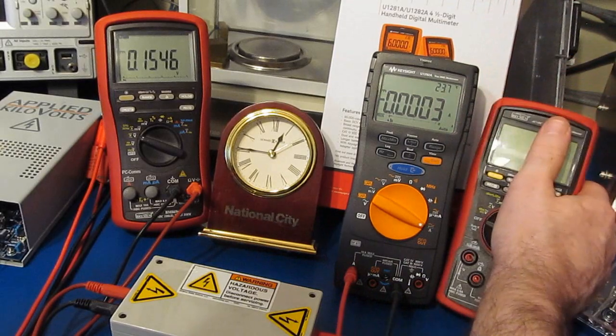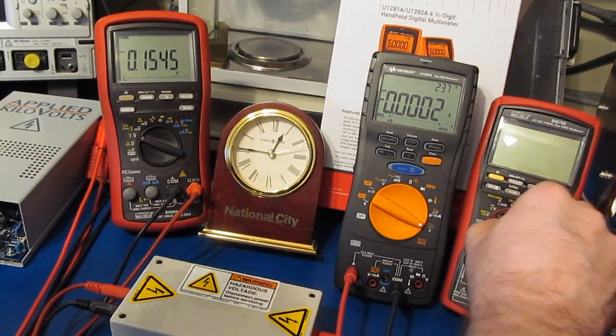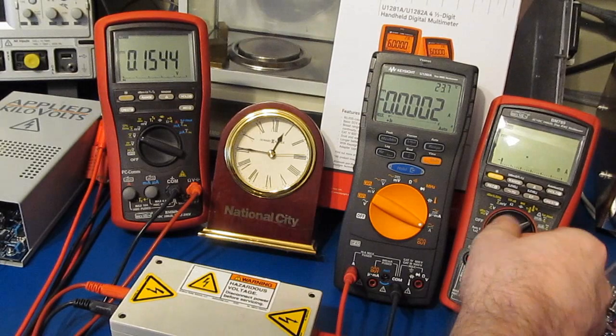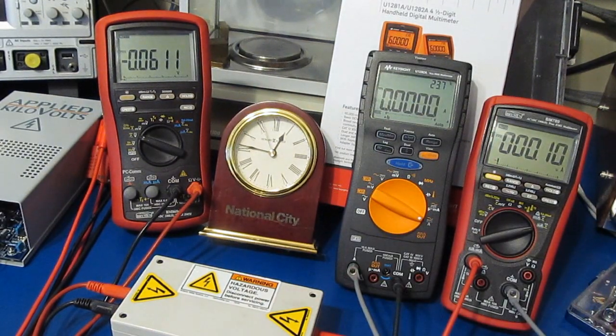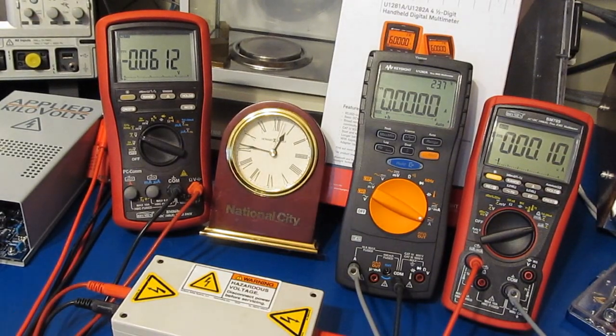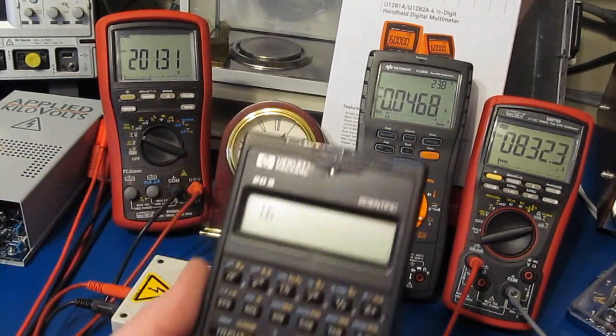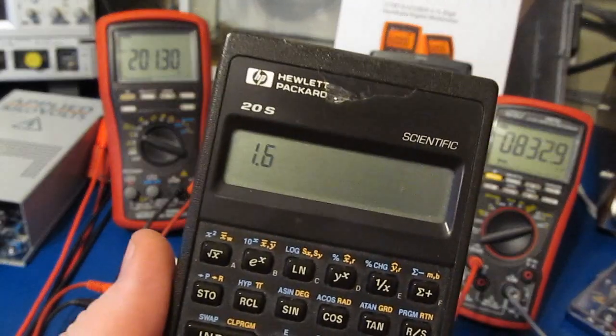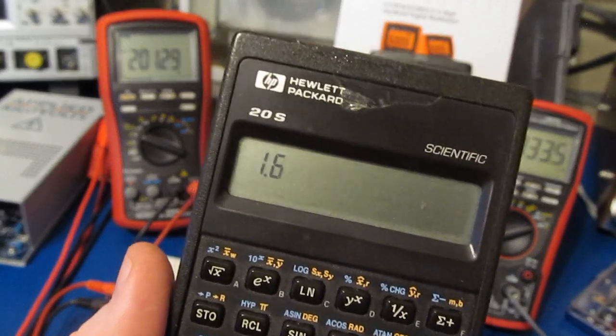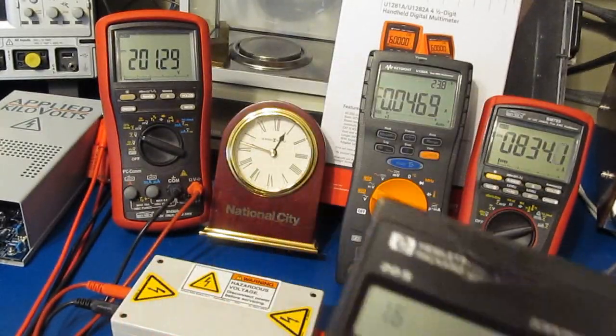Again, if you'd like to prove that, what we can do is we can just place one of our meters in series with it. Alright, let's go ahead and we'll turn on the power supply again. This should be roughly 800 microamps. And you can see it's about 832. And again, we'll just wait for 1 minute to go by. And of course, if we take the 2000 squared divided by our 2.5 mega ohms, that gives us 1.6 watts.